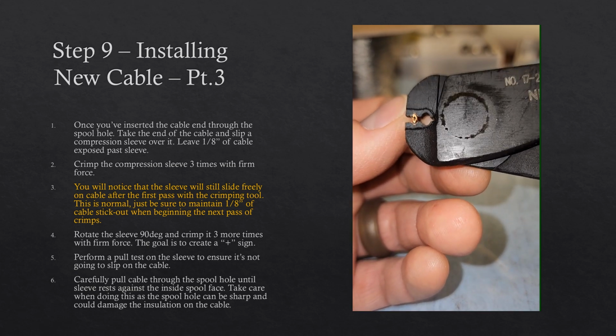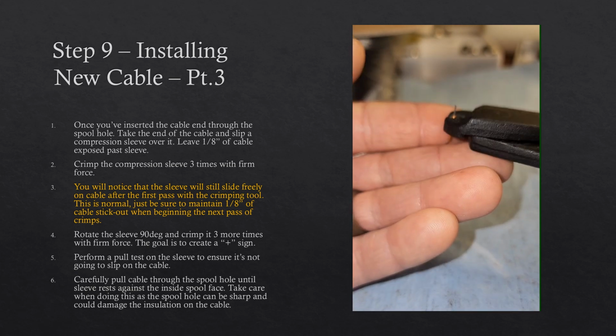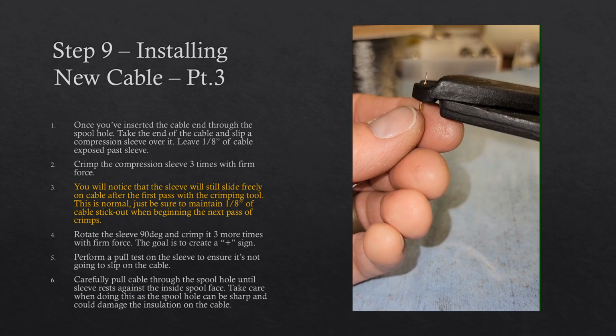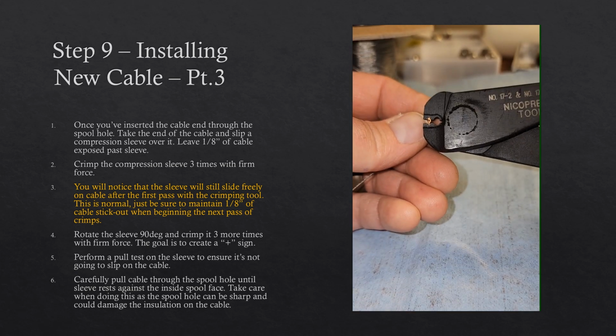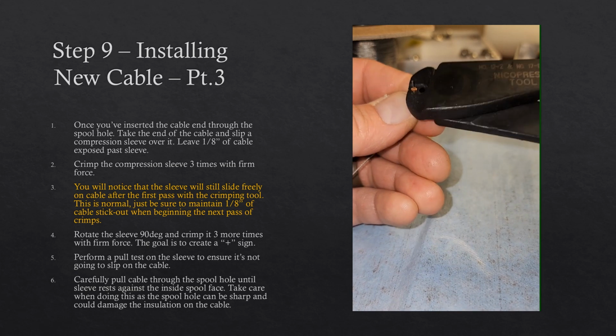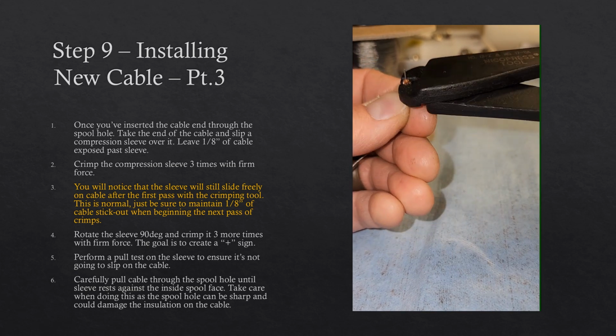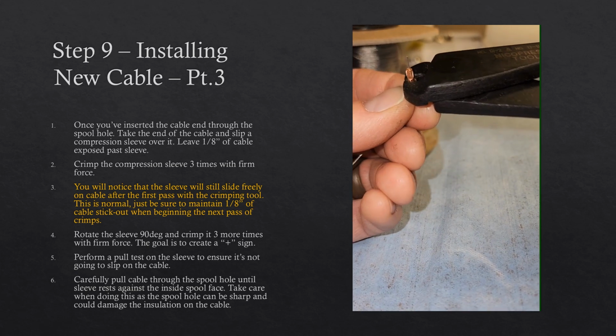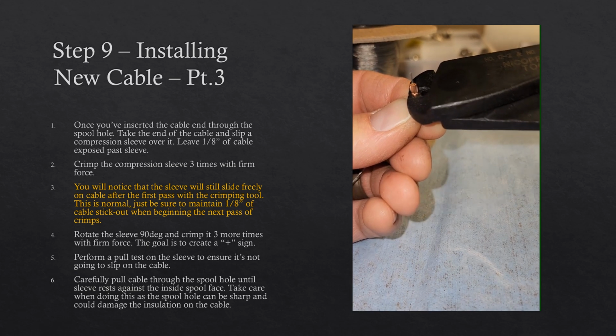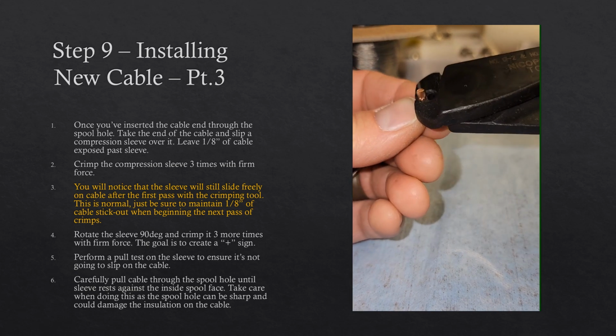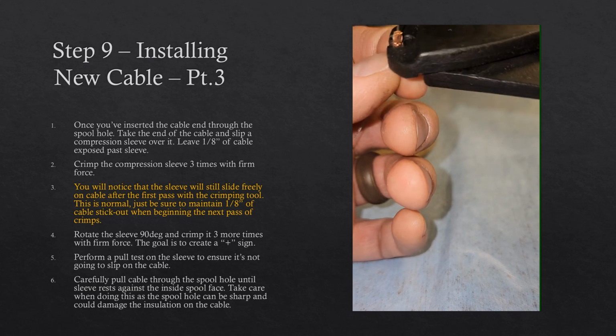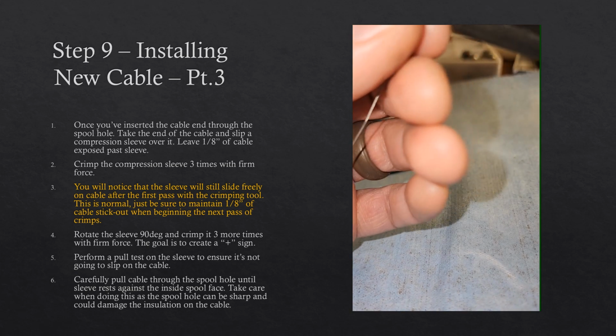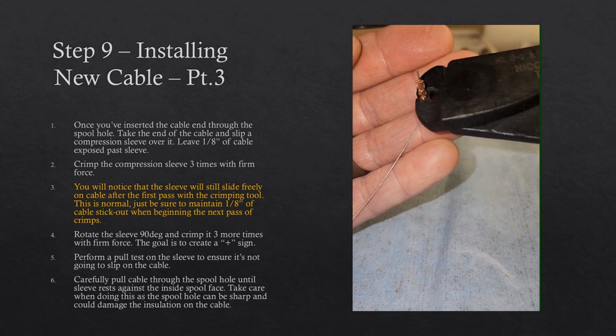Just make sure that cable is still sticking out about an 1/8 inch before you start your next pass. So rotate it 90 degrees, just like the other one. Crimp it 3 times. 1, 2, 3, creating that plus sign that we talked about earlier. A good amount of force.